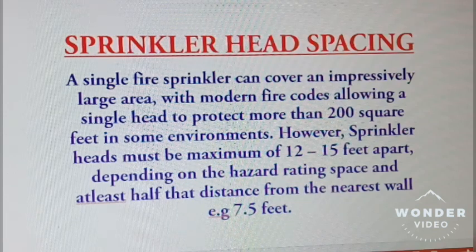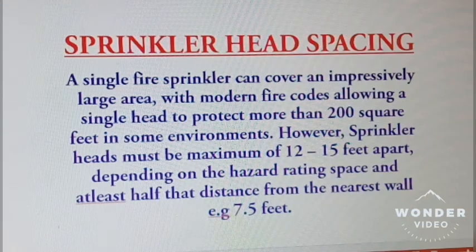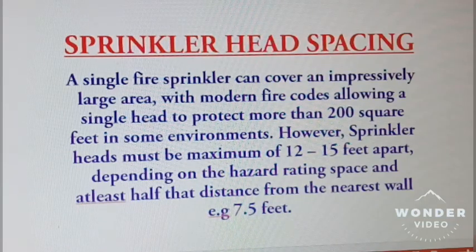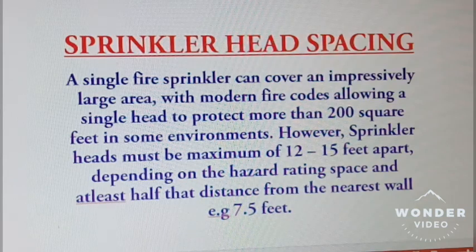Sprinkler head spacing. A single fire sprinkler can cover an impressively large area, with modern fire code allowing a single head to protect more than 200 square feet in some environments. However, sprinkler heads must be a maximum of 12 to 15 feet apart depending on the hazard rating space, and at least half that distance from the nearest wall, e.g. 7.5 feet.